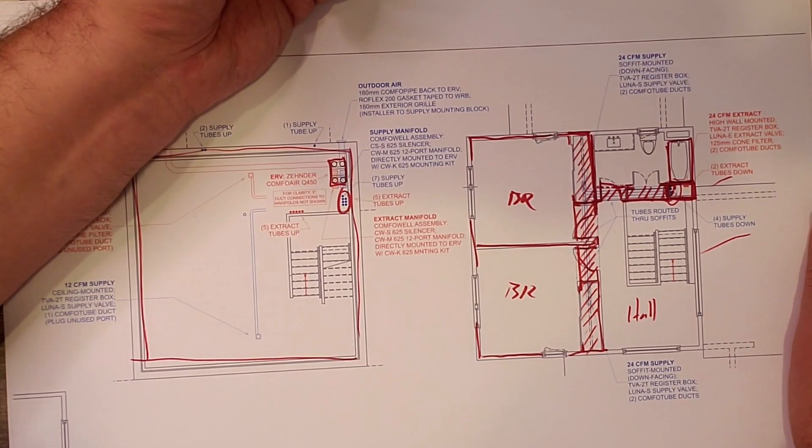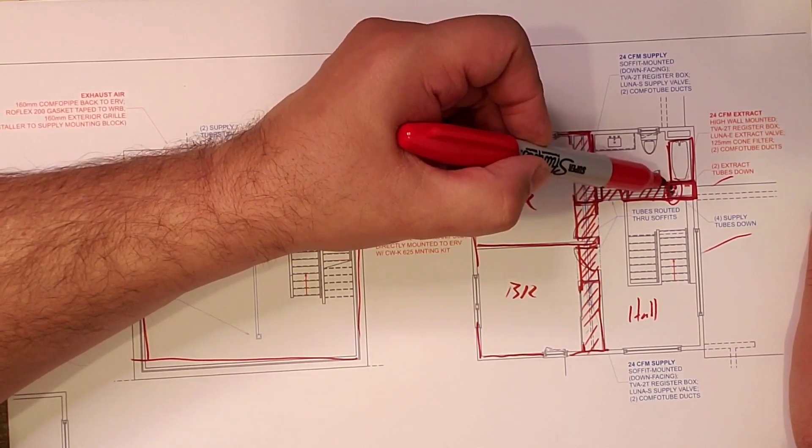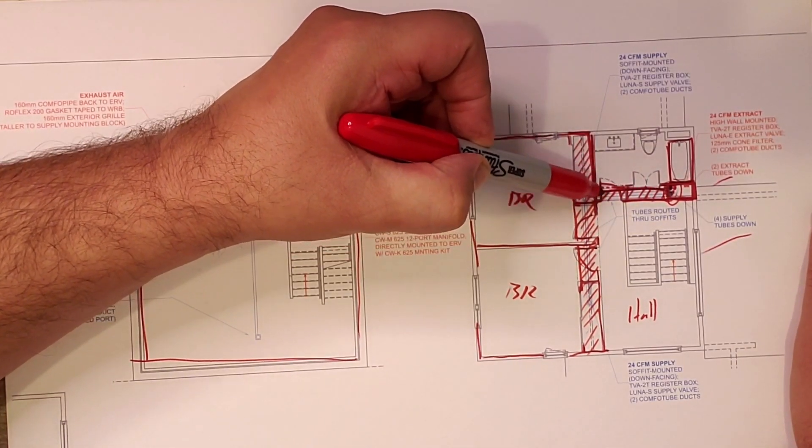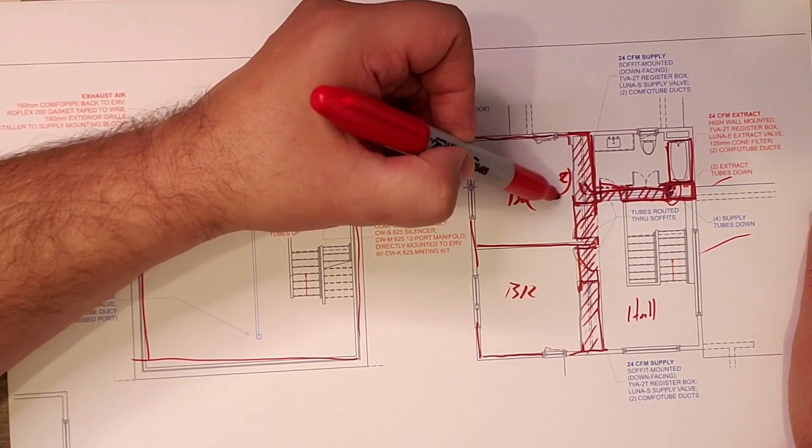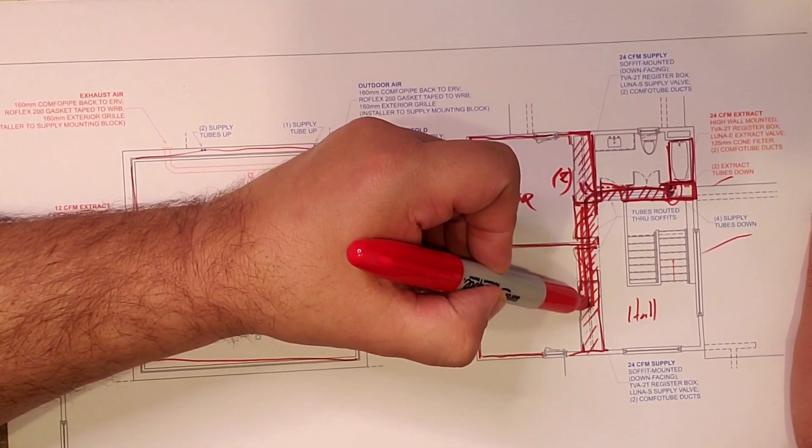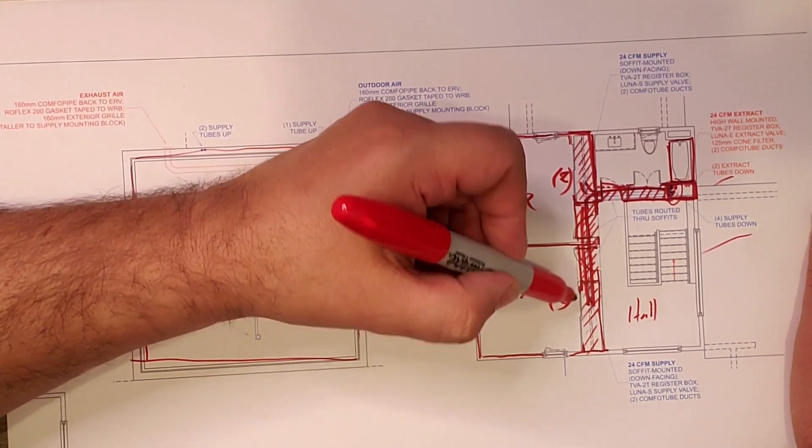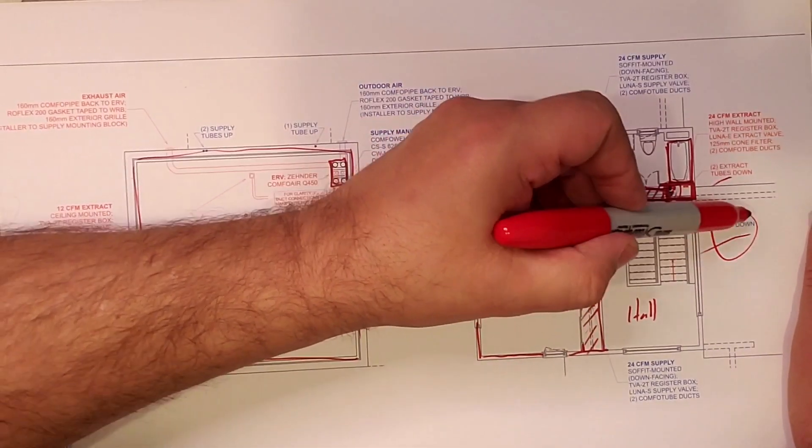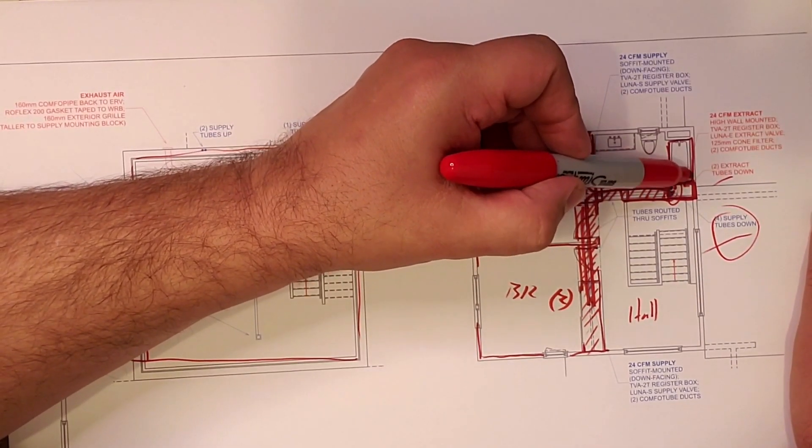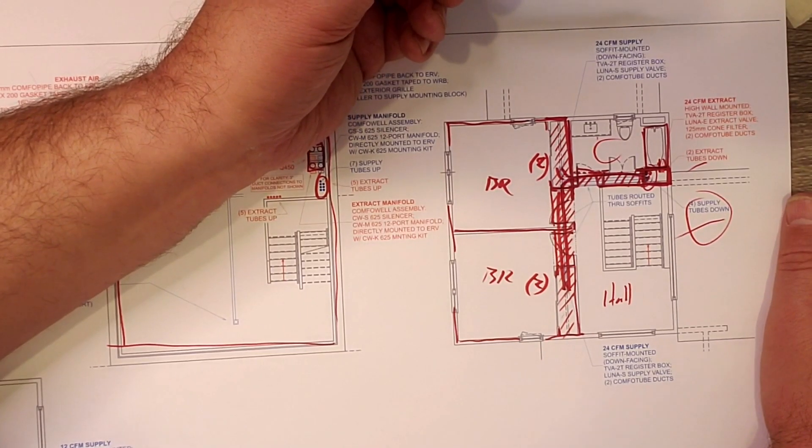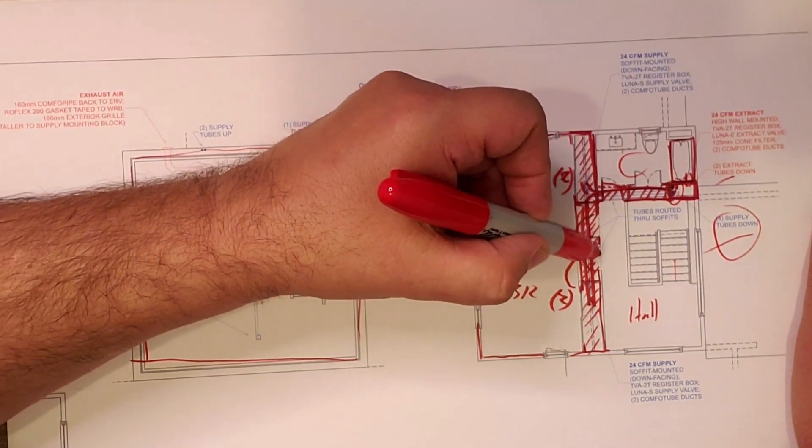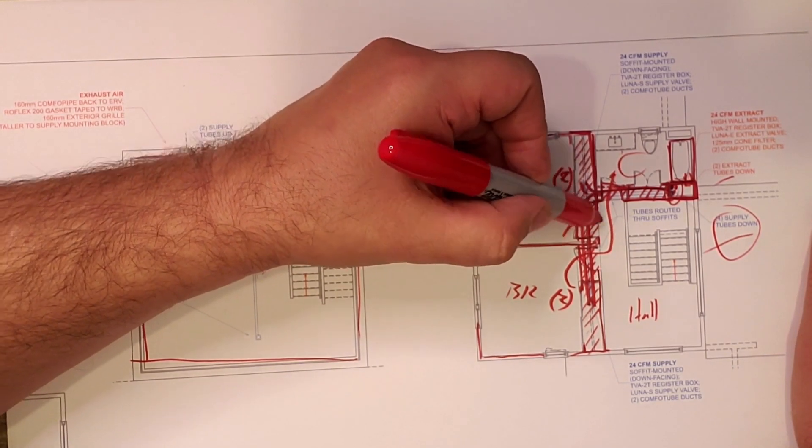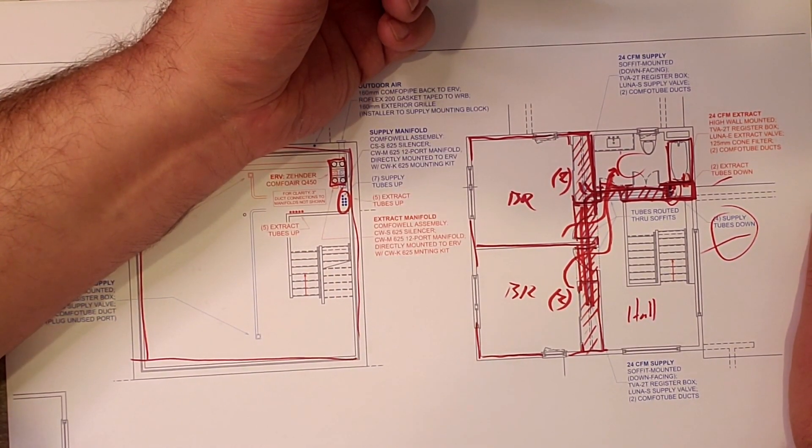So you can see four supply tubes and two extraction tubes. So basically pulling air out the extraction and four supplying. Now those four supplying are two to each of the bedrooms. And so I did the initial layout where we put a linen closet there intentionally and obviously it feeds the bathroom. But the nice thing about having that linen closet there is we can continue this soffit and that gets pipes from that vertical chase into a horizontal chase that comes across and then it plugs in to the back side of this bedroom closet.